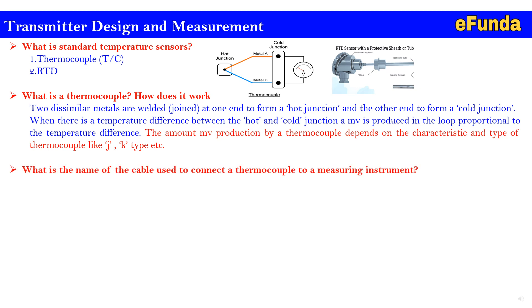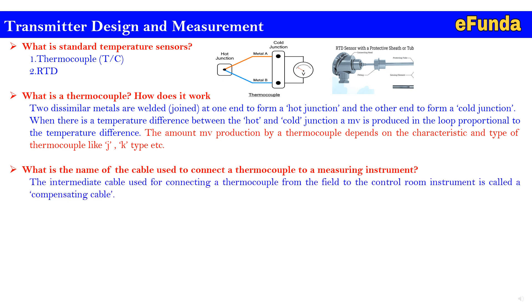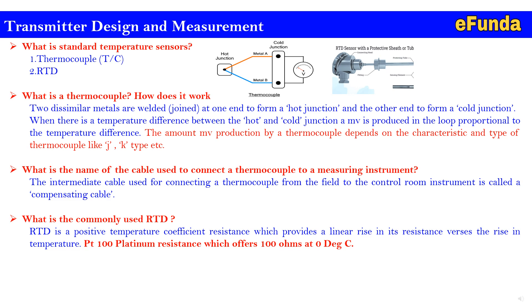What is the name of the cable used to connect a thermocouple to a measuring instrument? The intermediate cable used for connecting a thermocouple from field to the control room is called a compensating cable. What is RTD and what is the commonly used RTD? RTD is a positive temperature coefficient resistance which provides a linear rise in its resistance versus the rise in temperature. PT100 is a platinum resistance that offers 100 ohms at 0 degrees Celsius.